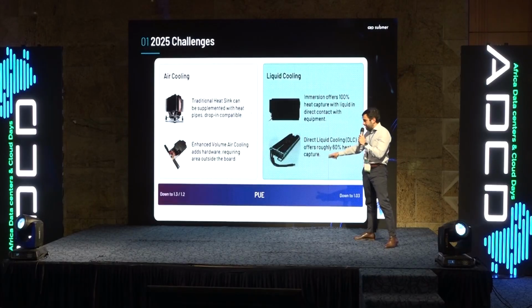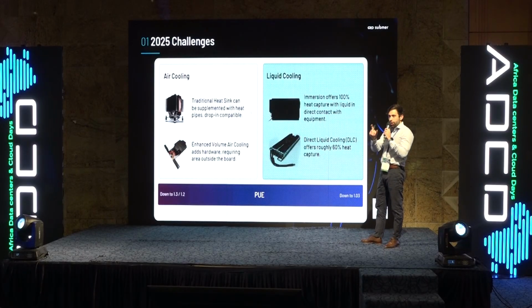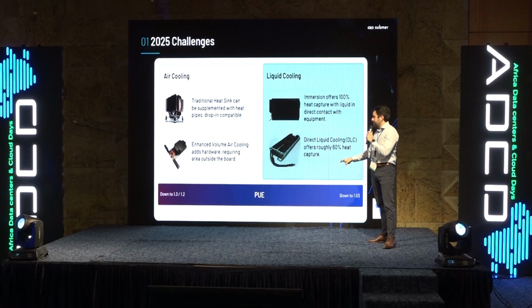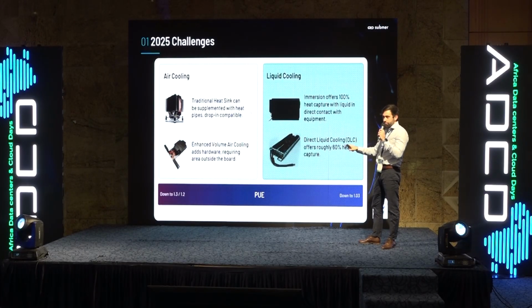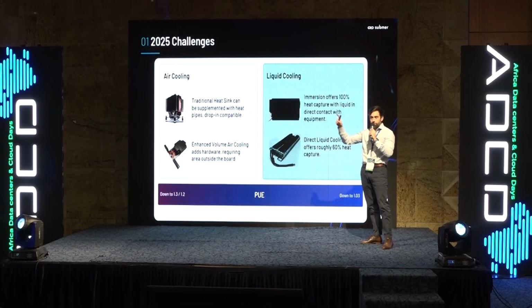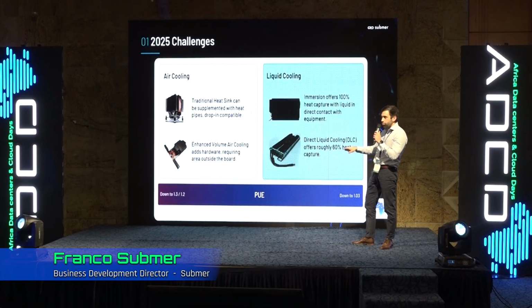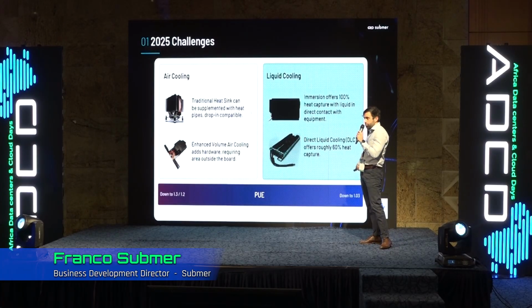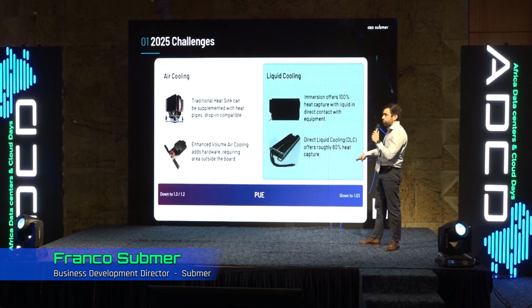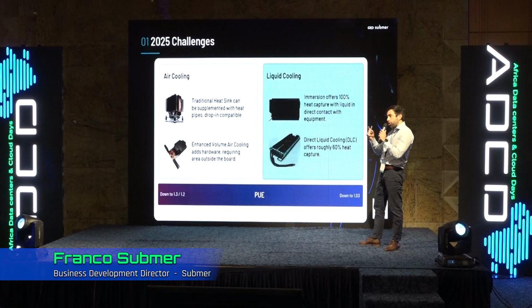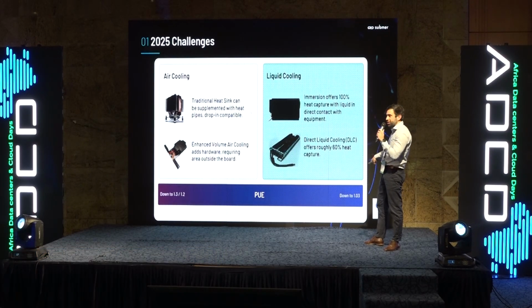Now the last thing about PUE, power usage effectiveness, the ratio between the total consumption of your data center and the IT consumption. Best case scenario, in countries like Finland or the Nordics, you might achieve a PUE of 1.3, 1.2. But when you go to immersion cooling, we can reach a PUE of 1.1. And the partial PUE related to the cooling system can go down to 1.03.